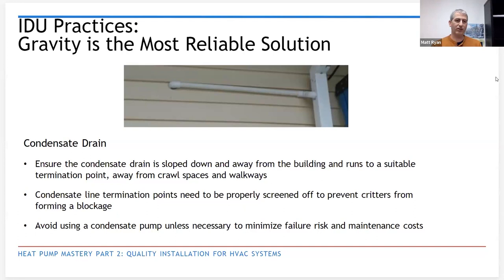Every time that thing cycles into defrost, you're going to get water, which then is going to refreeze, and that's why we elevate the outdoor unit. Wintertime, it's going to want to try to build up frost and ice, and so that's where that ends up. Which, as we're talking, I'm going to make a note of that. That might be a good thing to touch on while we're talking outdoor units.